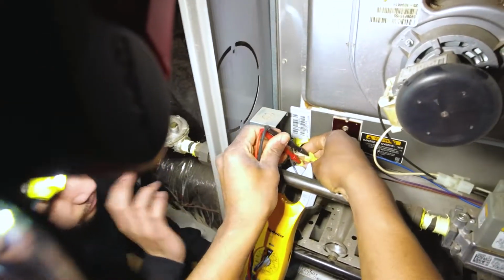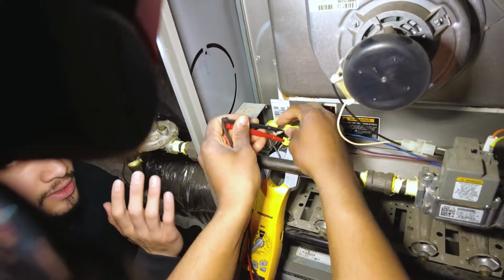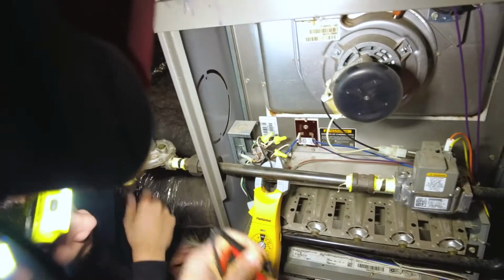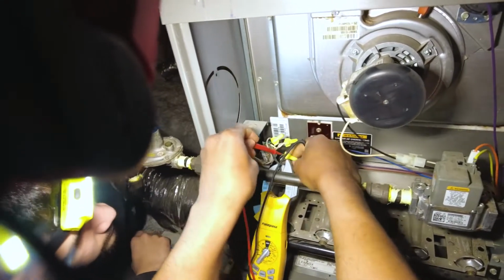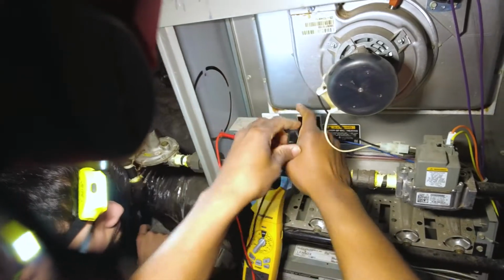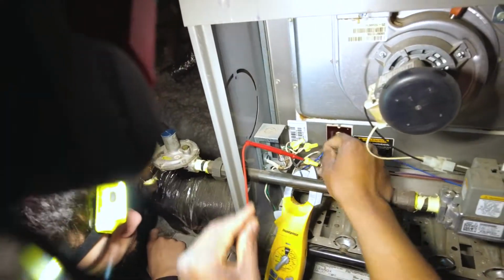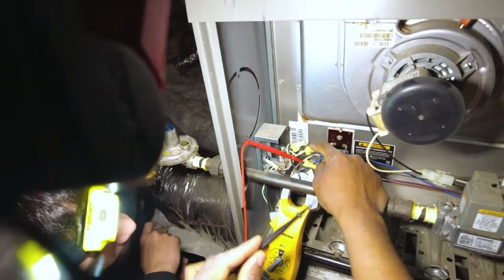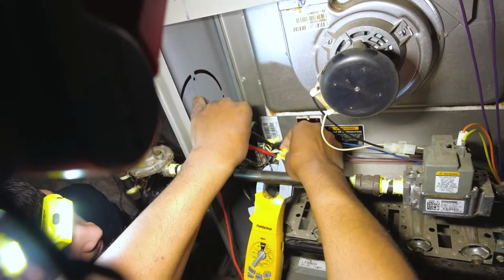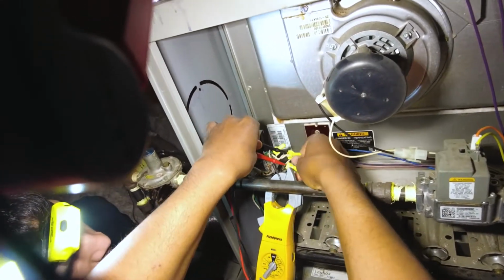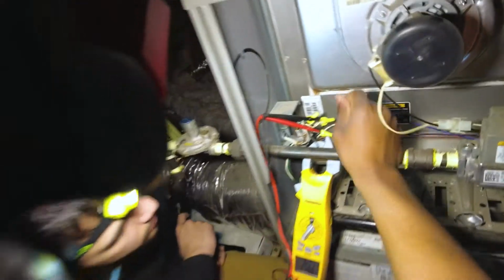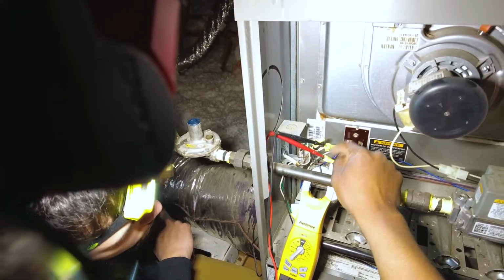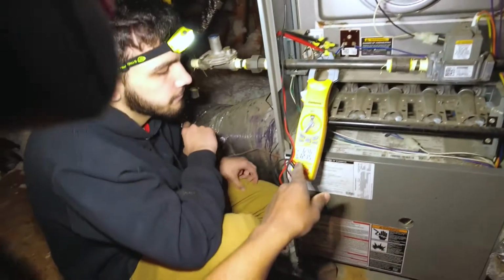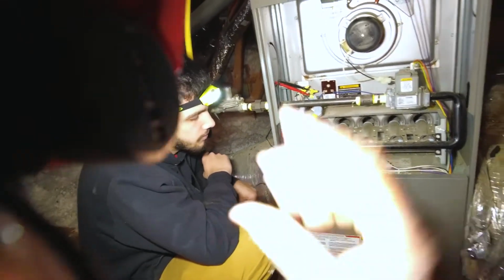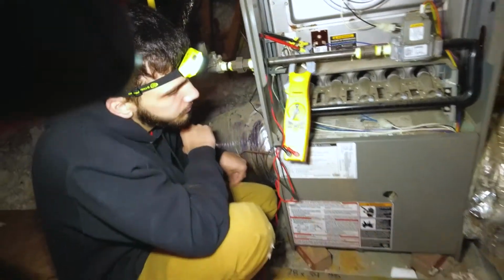I'm seeing it. So one set is the high voltage, the other set's the low, right? Oh yeah, so one is going to be your neutral, which is essentially, it's not a ground, but it's just a... this black is the hot leg. You will not get electrocuted if you do touch the neutral, but just don't. Either way, this is checking reference between the two, checking voltage between this ground here and this neutral. So we've got 121 volts, right? So 6 amps at 121 volts.